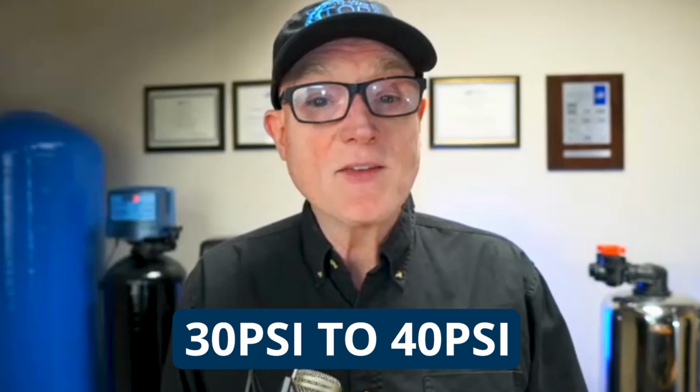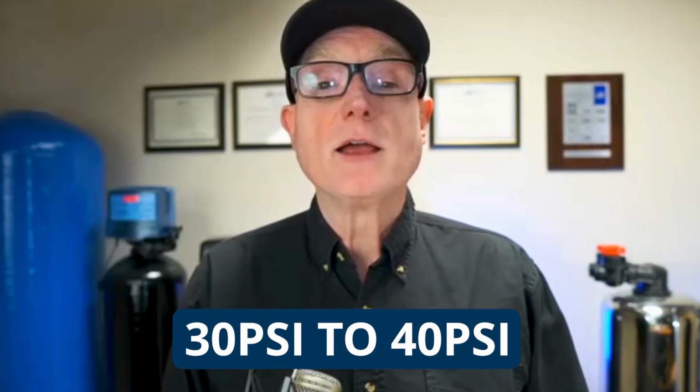But generally, one flow rate, and it turns on at one pressure and off at another pressure. So as an example, many home well systems are set up to turn on at 30 or 40 psi, pounds per square inch, and turn off 20 psi higher, say 50, 60, or even 70 psi. So you get a range, and you may even notice this in your house.